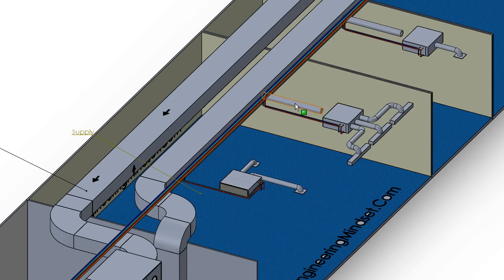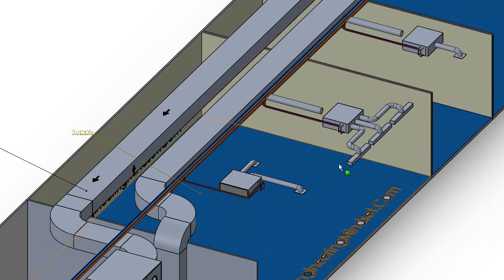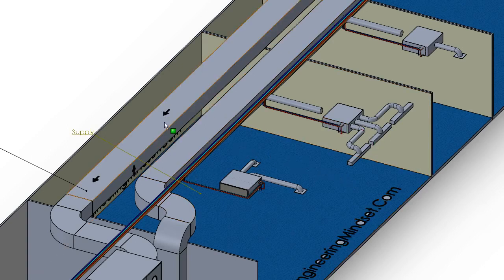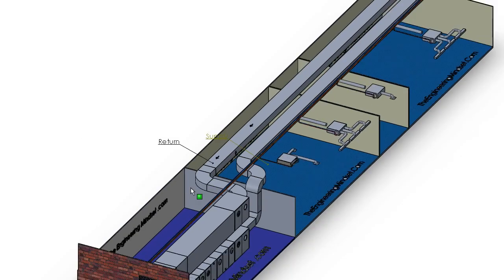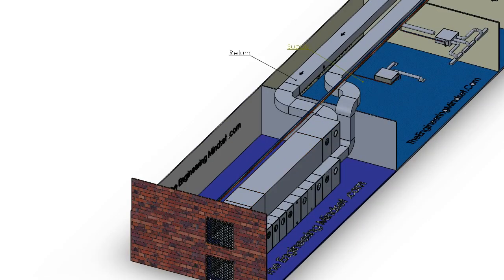This fresh air is directed into the inlet of the fan coil unit. It's usually not directly connected — there's a gap, and we'll look at the reason for that later. The fresh air enters the box, gets sucked in by a fan, gets heated or cooled, and is pushed out through diffusers into the space.